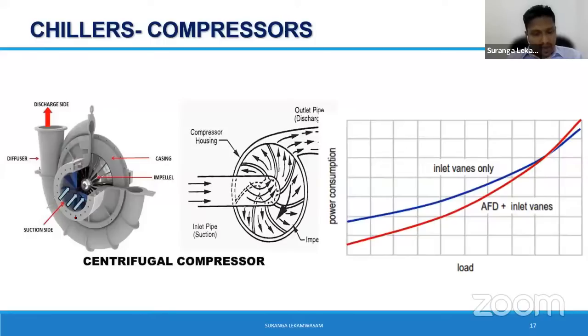So how do we load and unload the centrifugal chillers? Yes, the option is there for you to install a VFD drive and do the loading and unloading. That is possible. But instead of that, if you go for a non-VFD chiller, you can rely on inlet guide vanes. So inlet guide vanes you can use.